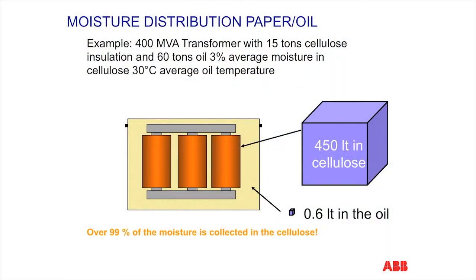As an example, a 400 MVA transformer with 15 tons of cellulose insulation and 60 tons of oil, with an average of 3% water in the cellulose, will equilibrate to 450 liters of water in the cellulose and 0.6 liters of water in the oil.